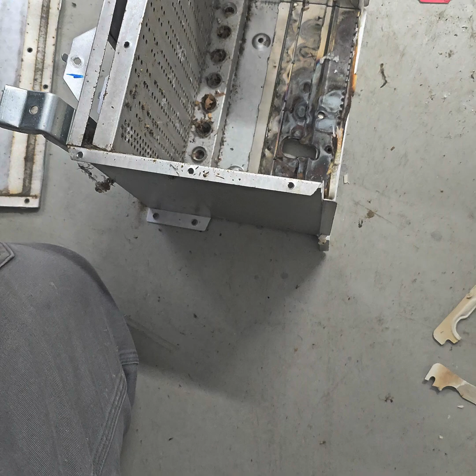So here's an area of the heat exchanger that you'll never see. This is the heat exchanger itself, okay? Right down here is where your gas is going into the combustion chamber. It's ignited, and it's getting hot because of the gases. Simultaneously, these were the holes that were always plugged. Now, remember, this is your air intake as well. So when these little holes are plugged because of lack of maintenance, that's plugging your system.